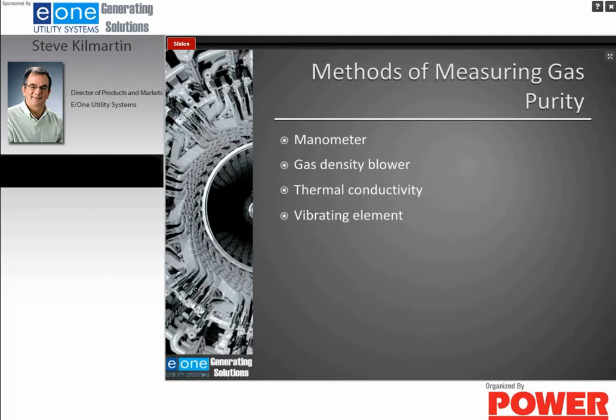You can also use gas density blowers to monitor hydrogen purity. This operates similar to a manometer. It's measuring differential pressure, and then that differential pressure is taken and converted into a purity. With a gas density blower, this is done electrically.